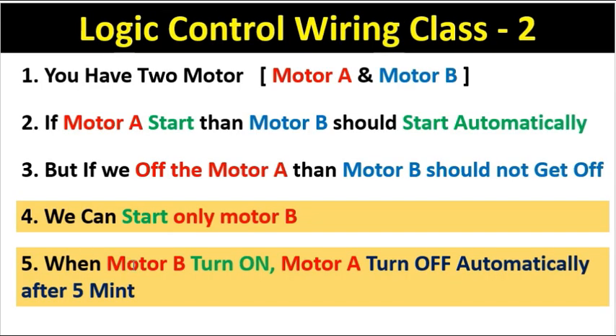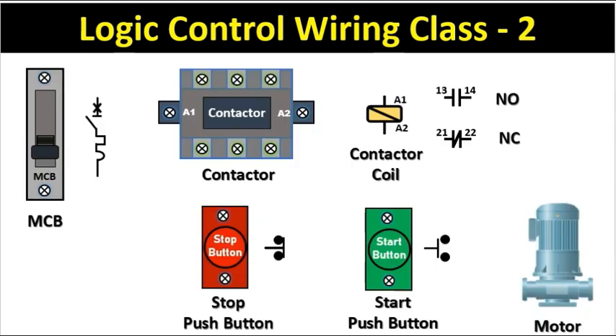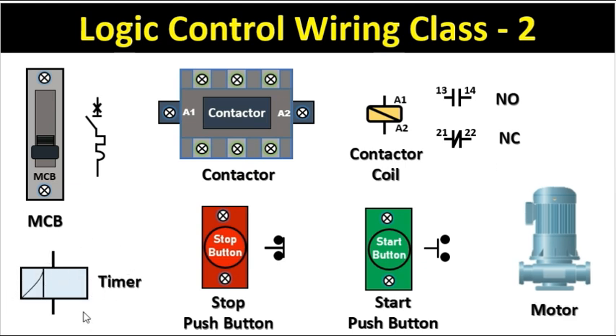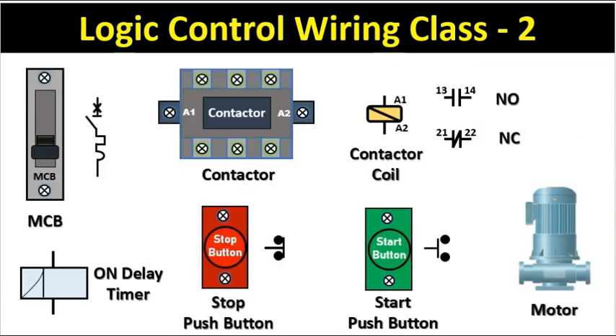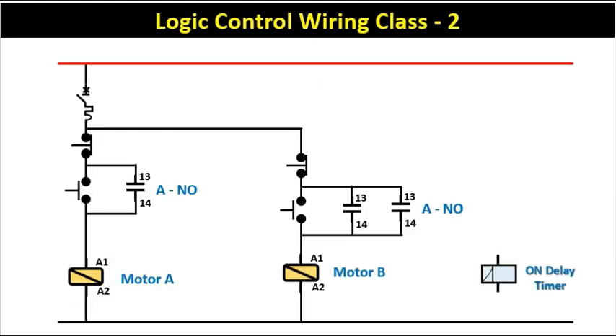Now, if we turn on motor B, motor A must turn off automatically after 5 minutes. Since there is a time condition, we have to use a timer. A timer is not among the existing electrical components shown, so I am adding a timer here. Since the logic says 'after 5 minutes,' we use an on-delay timer. I am copying this on-delay timer and pasting it into the circuit diagram.